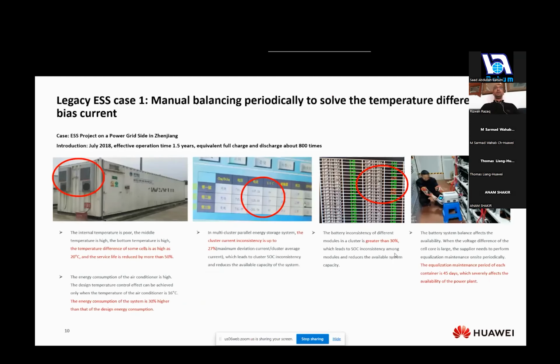So first of all, legacy ESS case 1: manual balancing periodically to solve the temperature differences and bias current. On a typical application available in the market right now, these batteries are containerized or fabricated into racks, and the control of the temperature within the facility is done on a case-by-case basis. Over the years, as the products age, what we typically see is a mismatch between the battery cells. This reduces all the factors mentioned in the previous slide, specifically the lifetime and the utilization of the batteries over their overall lifespan.